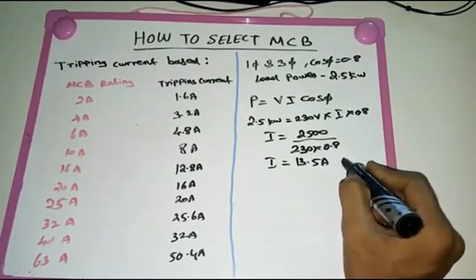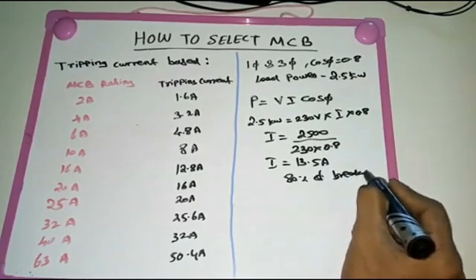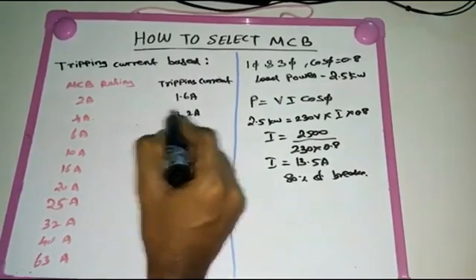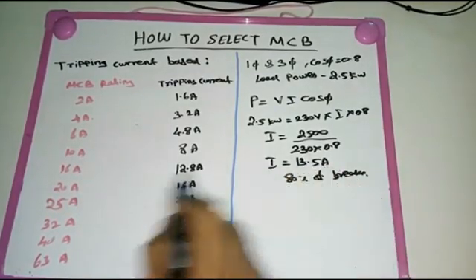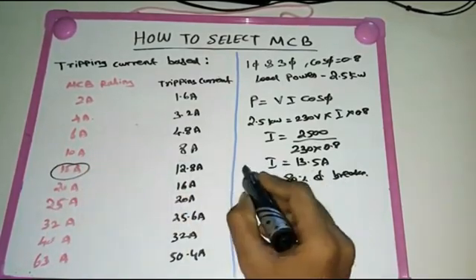We select 16 ampere because the MCB performs best when operating at 80% of its tripping current. For example: 2A MCB handles 1.6A load; 4A handles 3.2A; 6A handles 4.8A; 10A handles 8A. Since our load current is 13.5 ampere, we select a 16 ampere single pole (SP) breaker.